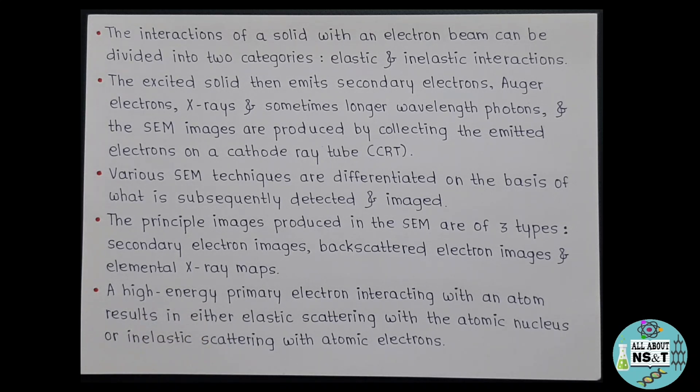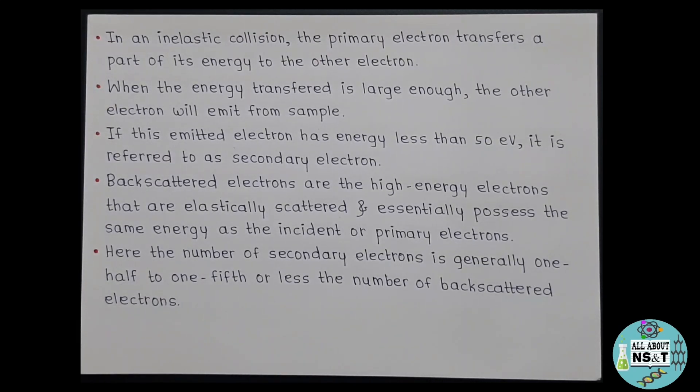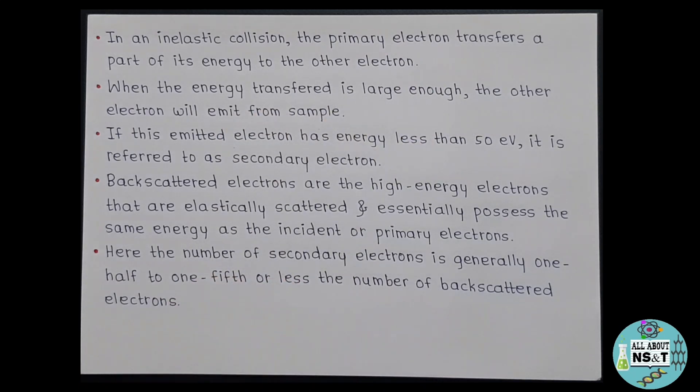Okay, now high energy primary electron interacting with an atom results in either elastic scattering with the atomic nucleus or inelastic scattering with the atomic electrons. So as we have discussed earlier, in an inelastic collision, the primary electron transfers a part of its energy to the other electron. When the energy transferred is large enough, the other electron will emit from sample. If this emitted electron has energy less than 50 electron volts, it is referred to as secondary electrons. The backscattered electrons are the high energy electrons that are elastically scattered and essentially possess the same energy as the incident or primary electrons. Here the number of secondary electrons is generally one half to one fifth or less the number of backscattered electrons.